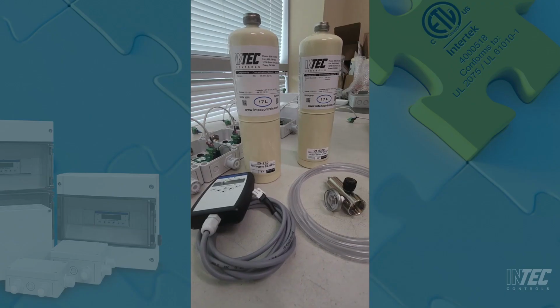This is Jim with INTEC Controls Tech Support, and today we're going to be going over how to calibrate a DT6-E1110-E carbon monoxide sensor using the PG2-STL6 handheld service tool. Prior to calibration, you want to make sure that you have all the required calibration equipment to calibrate with.